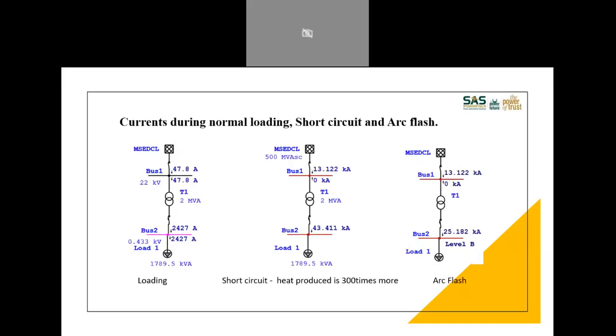Now let us see a live example of how much more heat is generated under these conditions. The left figure which you see is a normal 2 MVA transformer, let's say running with about 1800 kVA load. The HT side current will be about 47 amperes. The LT side current will be about 2427 amperes in this case. Now in this condition, if a short circuit happens at this bus 2, immediately your currents go to 13,122 amperes. You can see 47.8 amperes versus 13,122 amperes. Similarly, 2427 amperes go to 43,411 amperes.